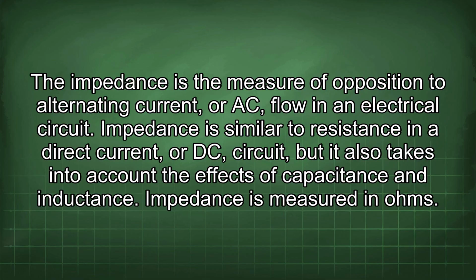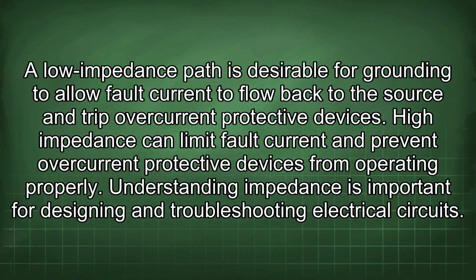Impedance is similar to resistance in a direct current, or DC, circuit, but it also takes into account the effects of capacitance and inductance. Impedance is measured in ohms. A low impedance path is desirable for grounding to allow fault current to flow back to the source and trip overcurrent protective devices. High impedance can limit fault current and prevent overcurrent protective devices from operating properly. Understanding impedance is important for designing and troubleshooting electrical circuits.